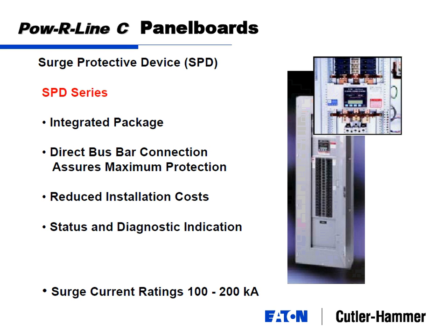So one of the things that we always recommend is when you're designing, look at what your panel board is feeding and determine if it's a good place for a surge protective device. If you put it on the panel board, it protects all transient voltages from all 42 branch circuits. If anything's on one line of that, it'll funnel up to the main bus. This will shunt it off the main bus, so the next classroom over doesn't see your transient overvoltages.